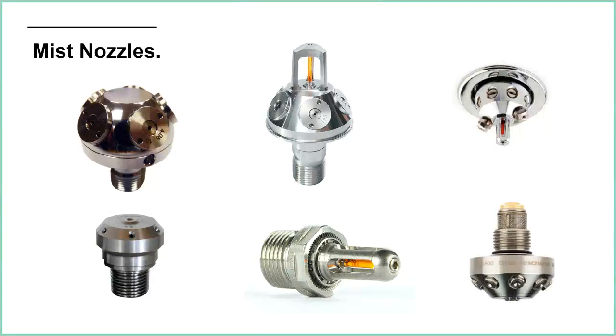You can see some of these nozzles have got glass bulbs. The one shown is yellowy orange, but you can get red ones as well. There is a red one on the screen, isn't there? So just like sprinkler heads, different coloured bulbs mean different activation temperatures. But you can see some of the nozzles haven't got glass bulbs in them, so they are designed to activate like a deluge system. All of the nozzles will go off at once, or in an area, depending on how the system's set up.